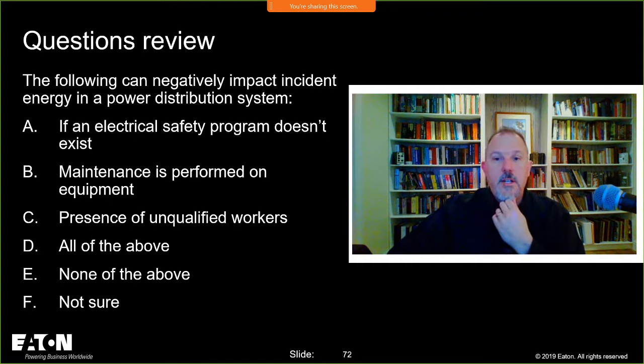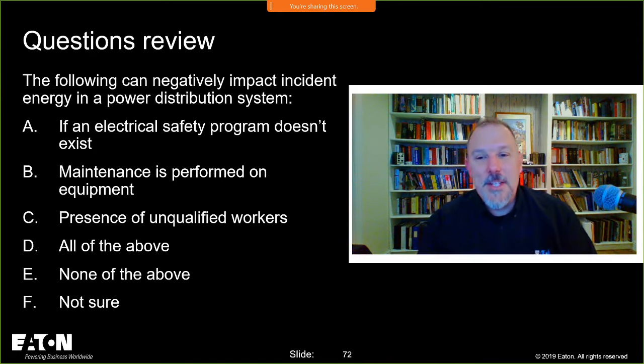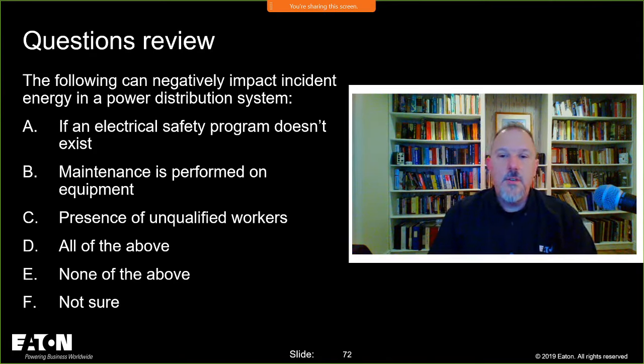As far as I understand, a current limiting device is a fuse or breaker used to protect another breaker by reducing the fault, but not completely interrupting it. And then that allows the other breaker to trip and complete. Yep. So, that was a question. I thought it was a statement. No, not quite right. Not quite right.